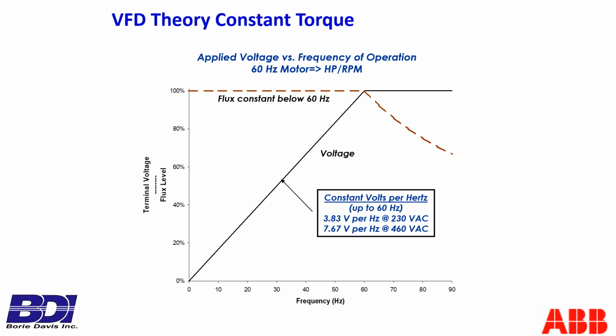All right, so here we have the graph of what we've been doing mathematically. Horizontally here is the frequency in hertz. That is what we apply to the stator. As well, the voltage is on our vertical axis. The motor voltage, called terminal voltage here, relative to frequency. And the flux level, the torque available, is represented by this brown dash line. And the power, the horsepower, the power required is along this vertical axis.